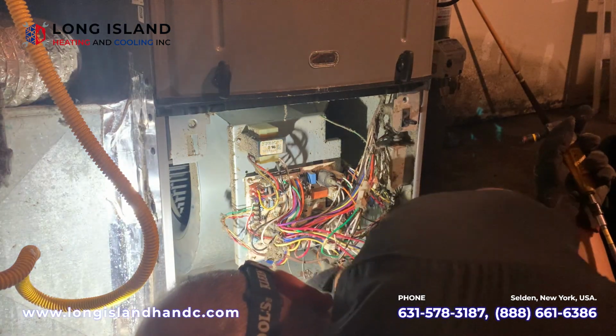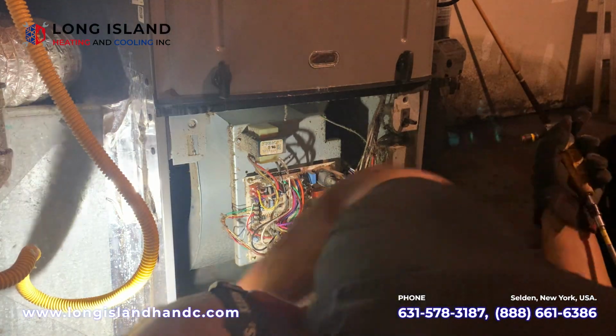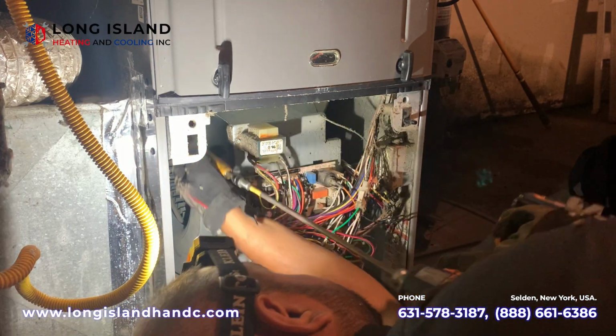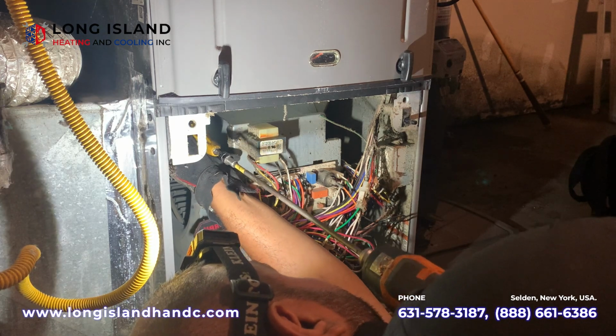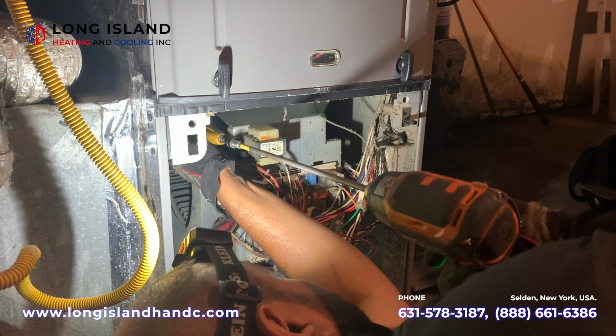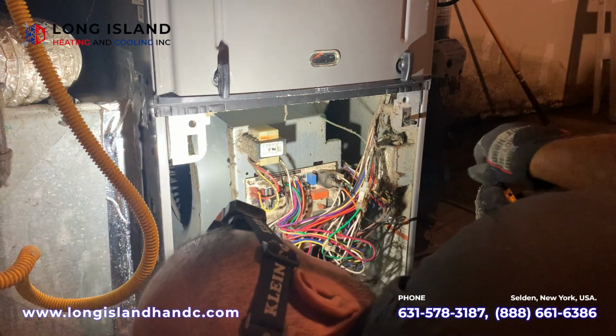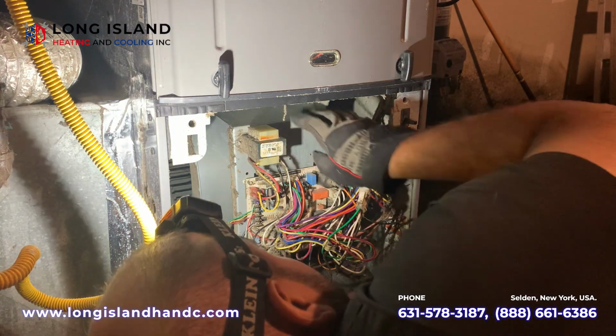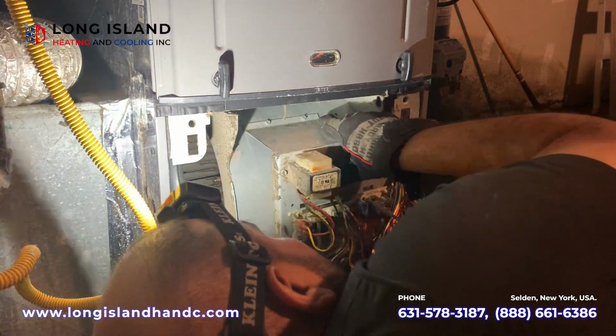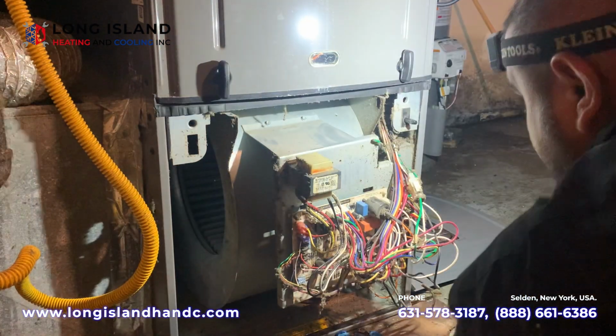So when you do troubleshooting on a blower motor, you have to make sure it's not the control board. Every time you troubleshoot, check the control board, check the blower motor, check all the wiring, just to make sure whether it's the ECM motor or the board.